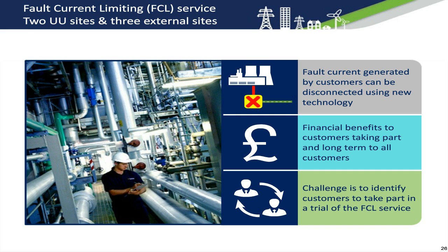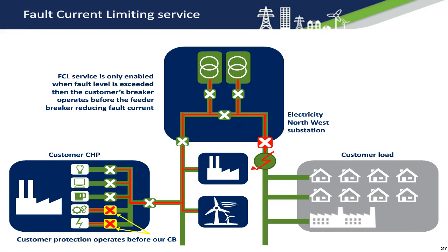The fault current limit service could work like this. In this example, electricity flows through the 2 transformers to the factory on the left and the homes and businesses on the right. At the factory, different types of equipment are connected to the network, including a large motor and a generator. A fault occurs again in this red squiggly line on the right. The fault current rushes towards the point of the fault. All protective devices start to operate, but the closest one to the fault operates first, disconnects the customers on the network beyond that fault.